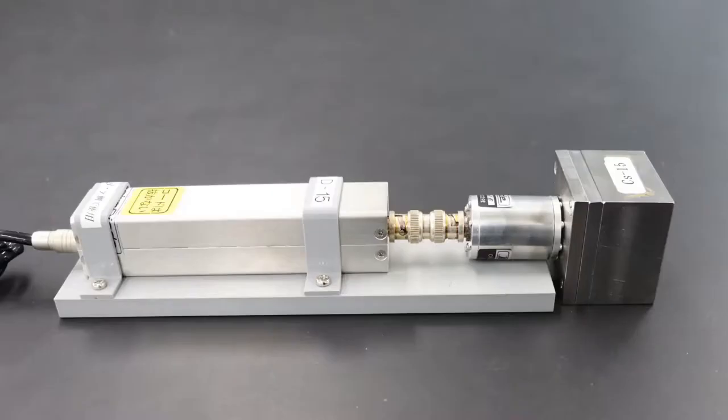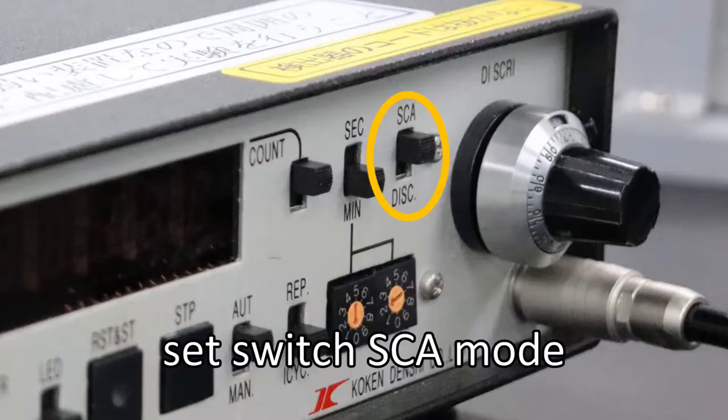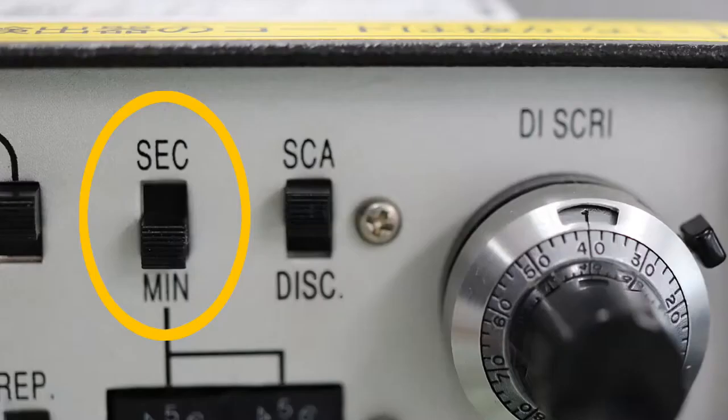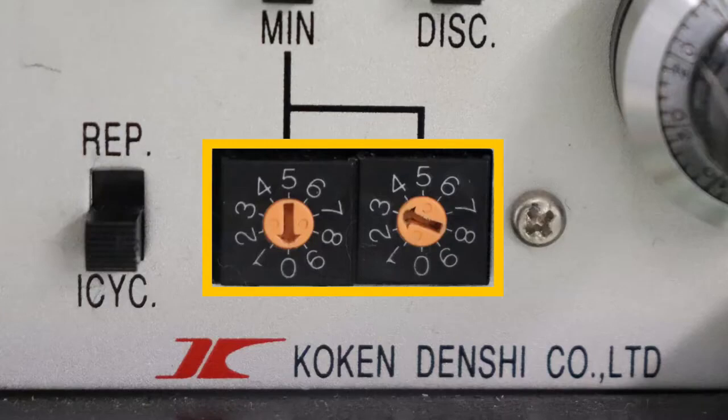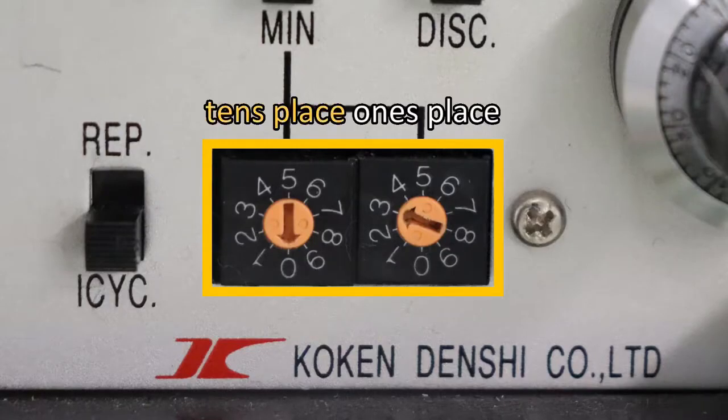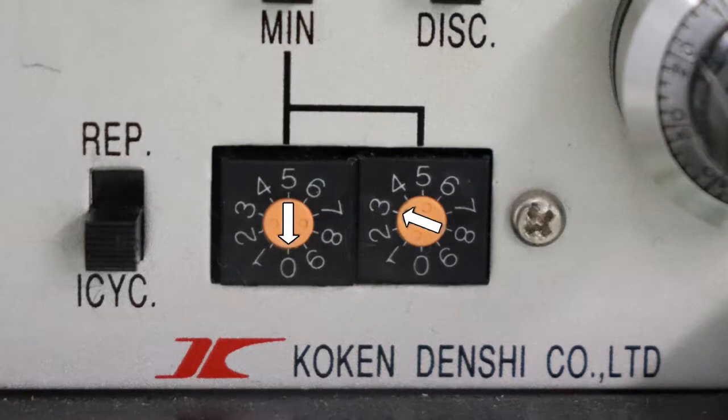Place the source snugly in front of the detector. Switch from DISC mode to SCA mode. This is the switch to change the unit of the measurement time between seconds and minutes, where SEC is seconds and MIN is minutes. Set it to minutes. These two dials are used to set the measurement time. The left side represents the tens place, and the right side represents the ones place. The dials have arrows on them. Read the number that the arrow is pointing at.